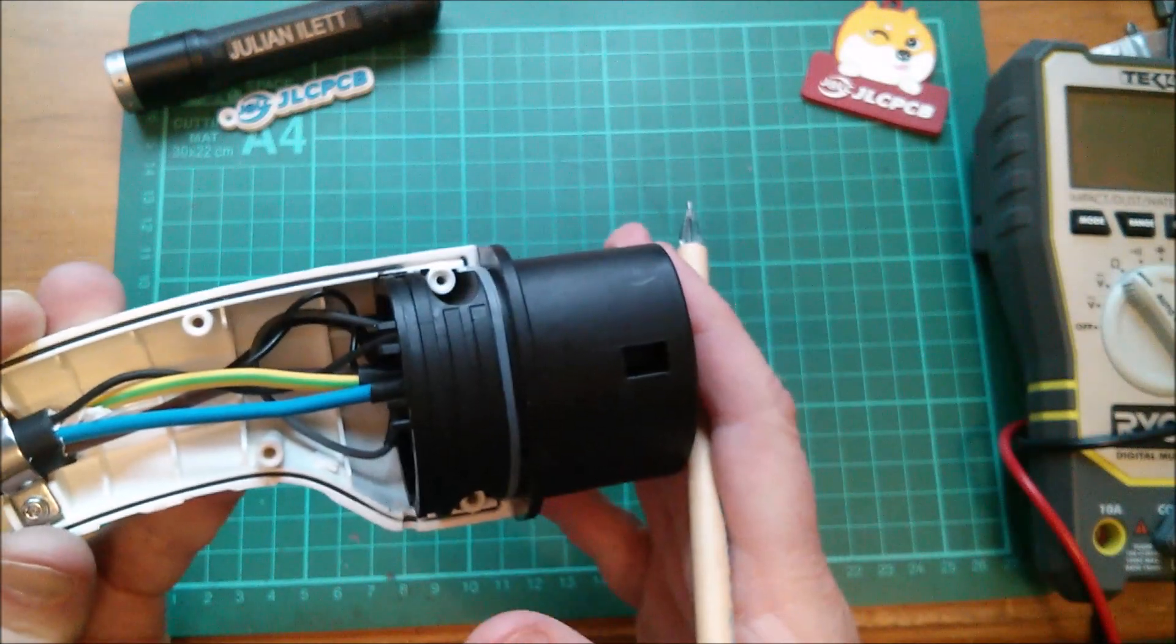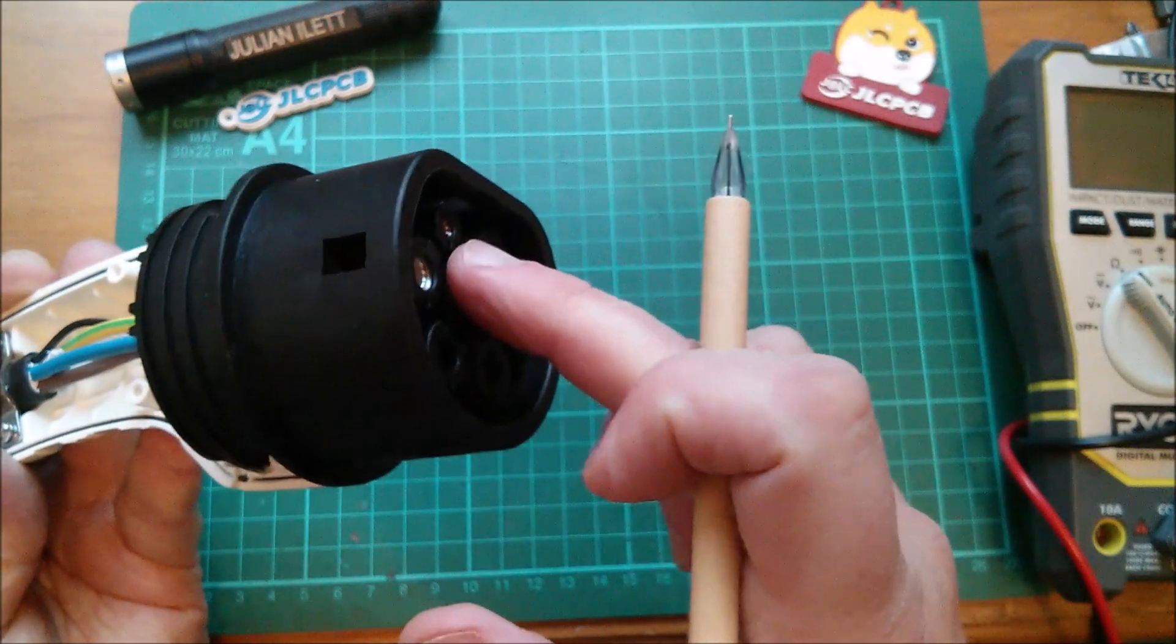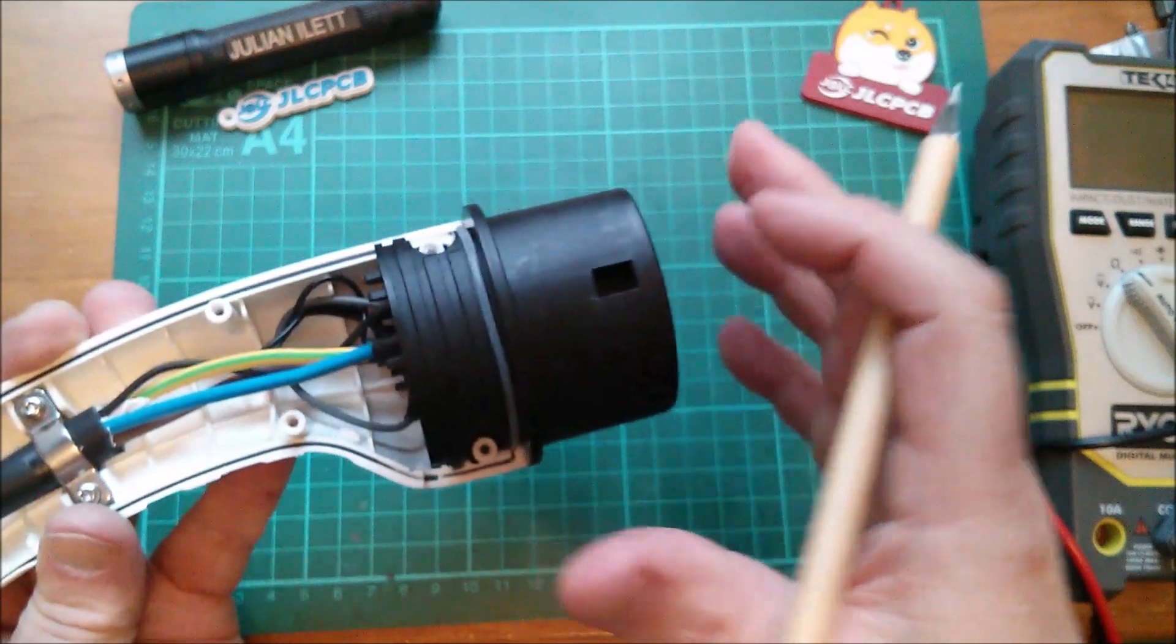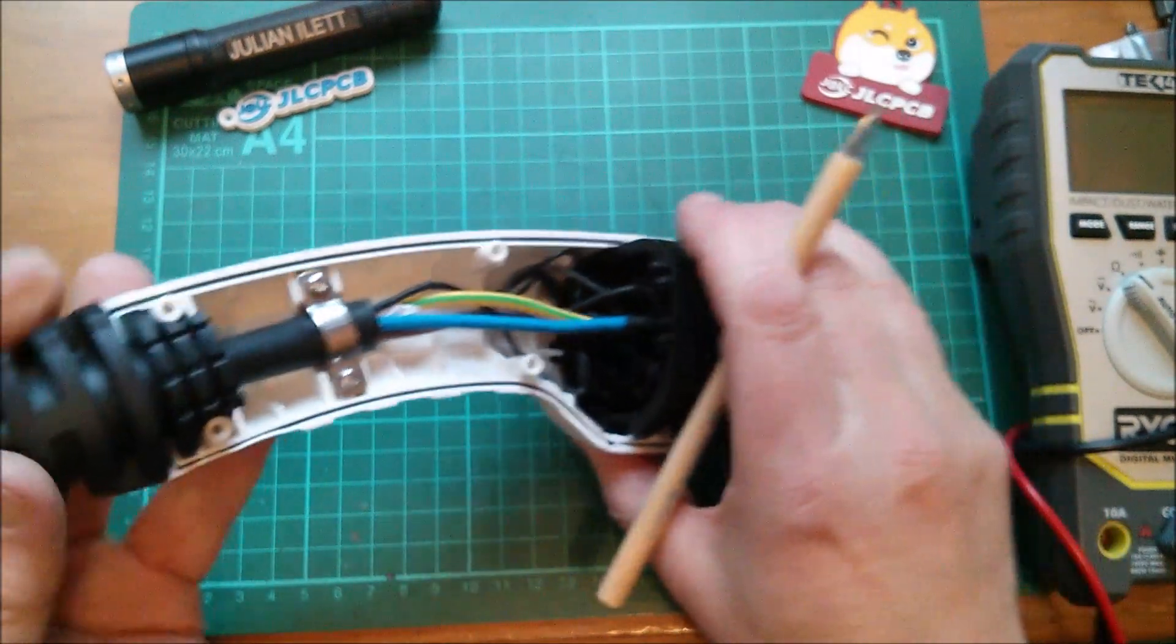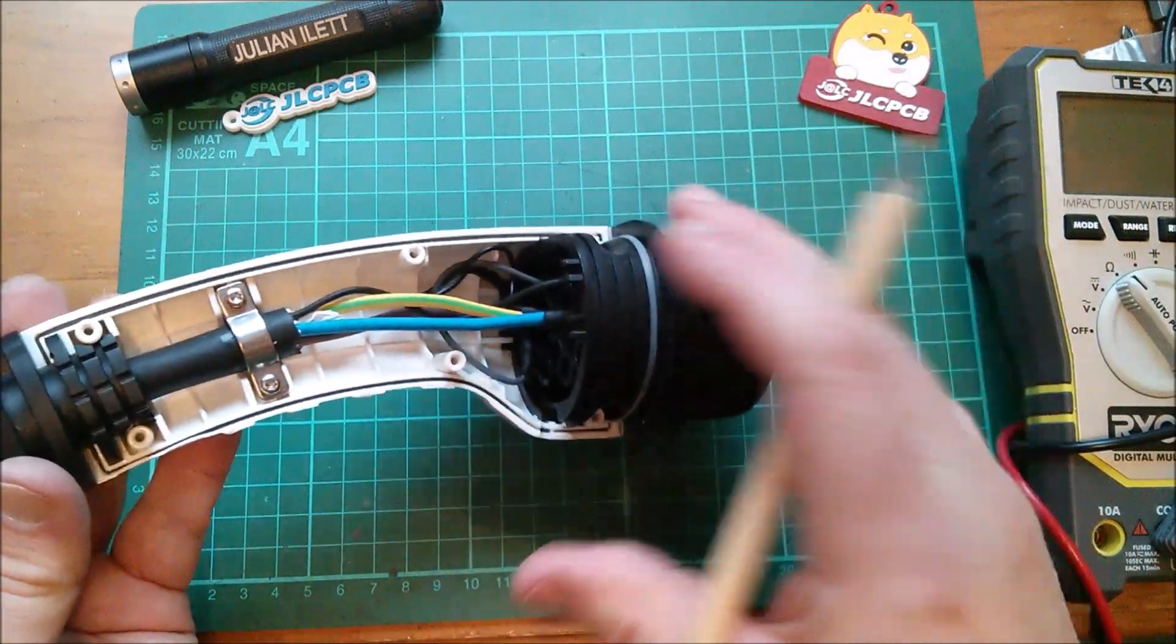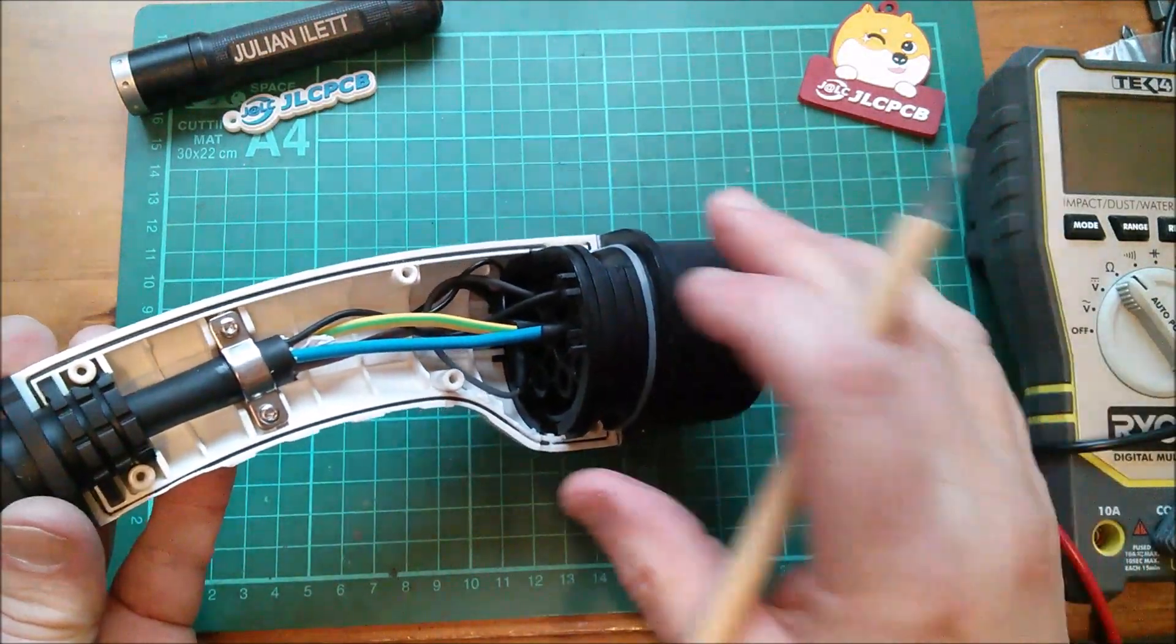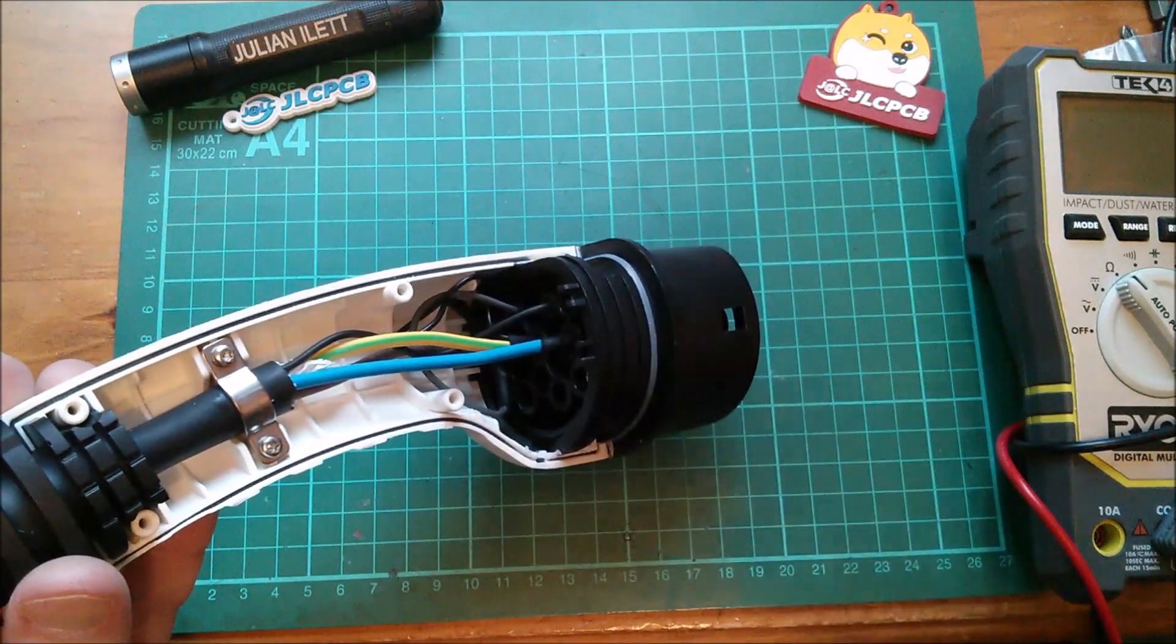And that tells the car, don't pull more than a certain current, despite what you're being told with the pulse width of the CP signal. Don't pull more than a certain current because the cable assembly, which may have a plug at both ends and may have been supplied with an underspecced cable, the cable assembly can only handle a certain current. So that's what that resistor does.